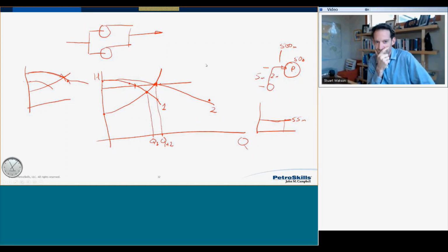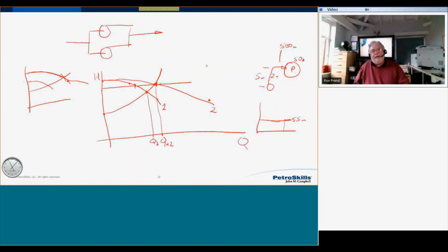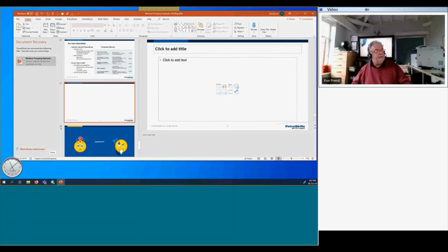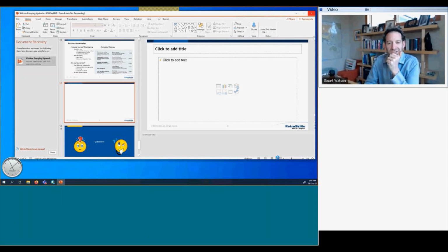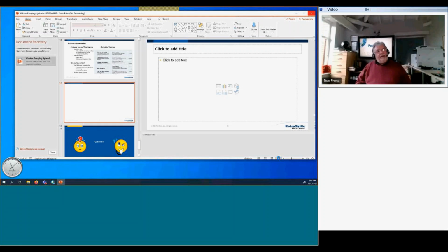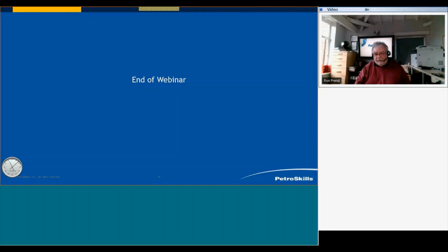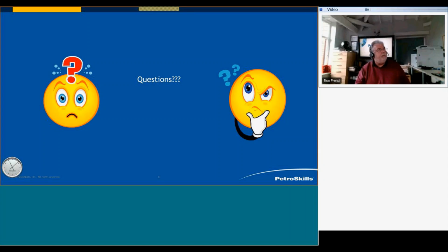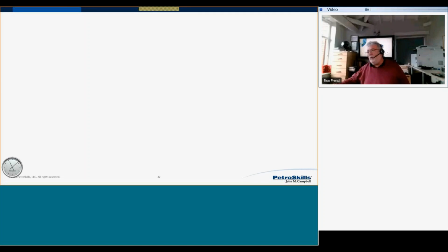You know, the temptation is, I've seen it so many times. You start off by saying, in fact, I've got to clear all this off now, haven't I? I'll just go to my annotation and bring it on again. Yeah, come on. The temptation is that if you come up with a design for the pump and you say, yeah, that's good, our pump is fine, but what about the future? Maybe we're going to open up some new wells, or we've got some reason that we're going to need more flow in the future. Let's increase the spec of the pump by 10%.